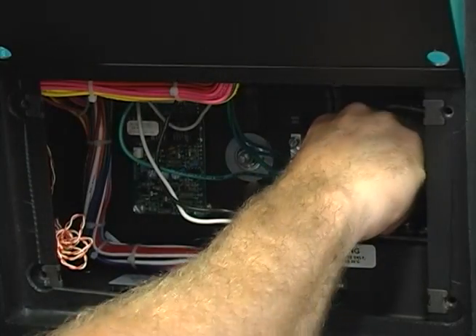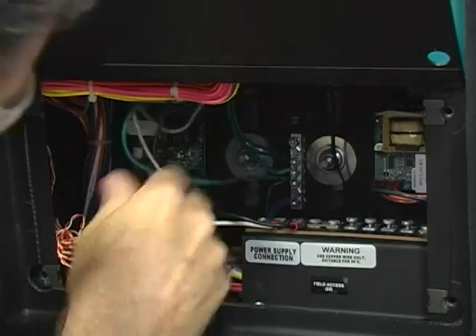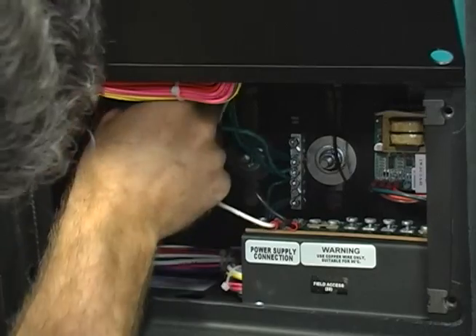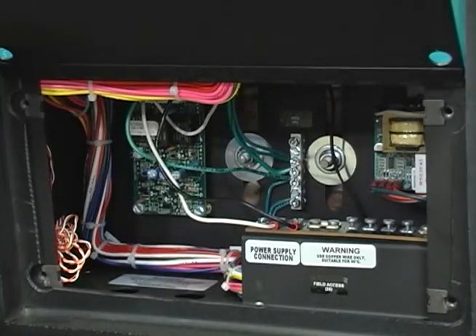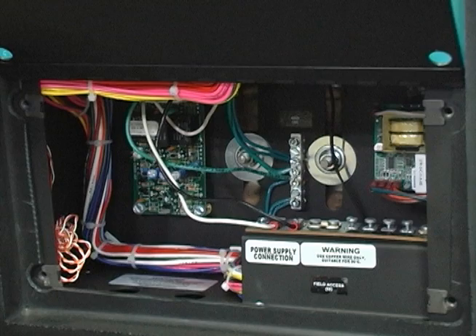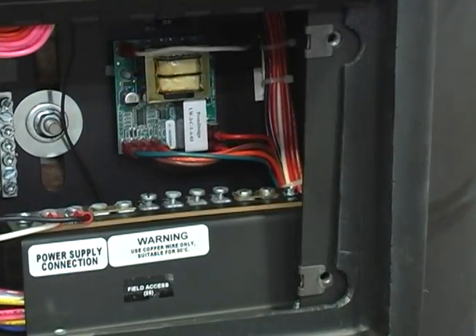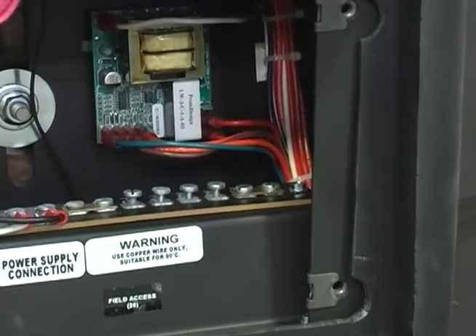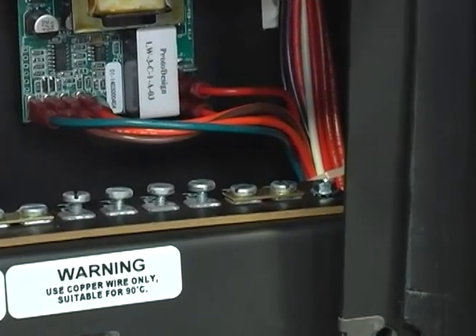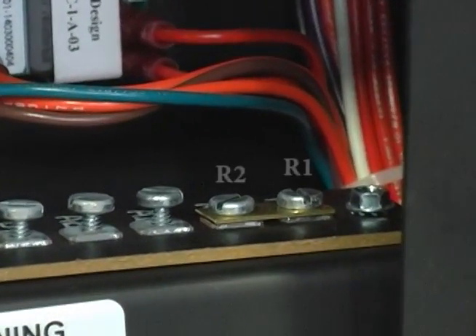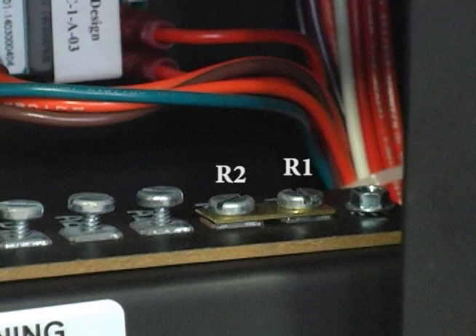After confirming the heater is not powered, visually and physically check that all electrical connections are tight by lightly pulling on the wires. Retighten any loosened connections that may have occurred during shipment. On the terminal strip, check to see if terminals R1 and R2 are jumpered. If they are, nothing more needs to be done. If the terminals are not jumpered but have wires connected to them, this indicates that a remote on-off relay is controlling the water heater from the building automation system.